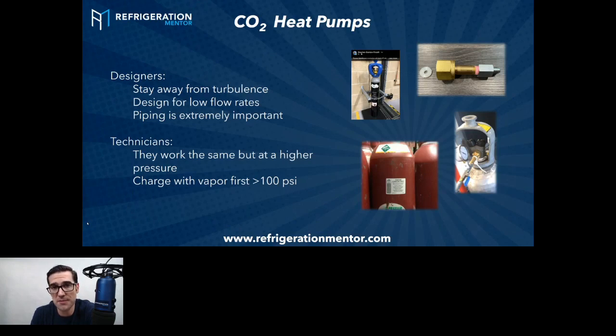This goes for any heat pump - if you don't design it properly, that COP of 2, 3, 4, or 5 is going to be reduced quite a bit, and that's not what you want. You're doing this to get more heat for less energy consumption - that's the whole point of heat pumps. So think about that when designing, any of you out there.